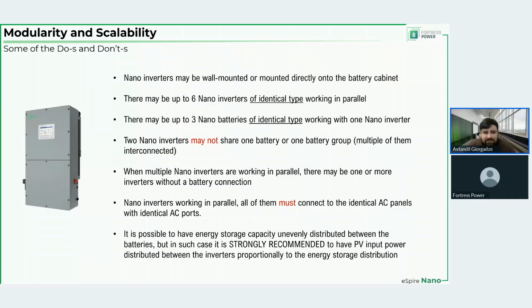You can have up to 6 inverters of identical type working in parallel. There may be up to 3 nano batteries of identical type connected per inverter, but that doesn't mean that if you have multiple inverters, that they need to have identical energy storage size. 2 nano inverters may not share one battery or battery group, but multiple batteries can share one inverter. Up to 3 batteries can connect to or operate from the energy provided by one inverter.